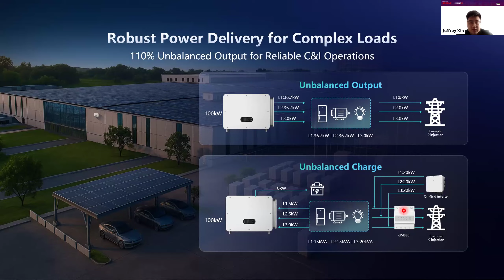If your inverter cannot support unbalanced output, it will output based on the average of the minimum of each phase. But if you can support unbalanced output, the sum of each phase could equal the rated power, while for different phases you can do different output or different charging power, just like that.